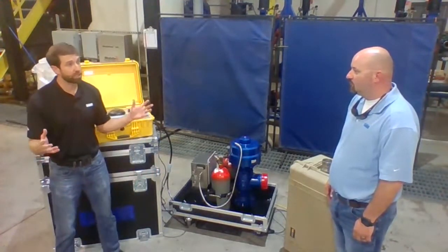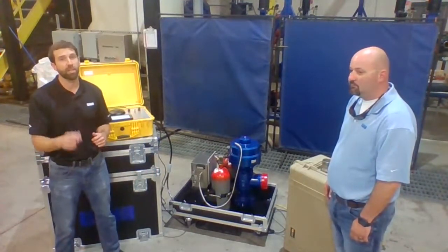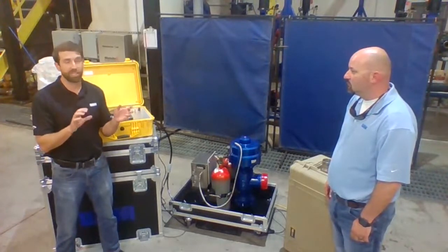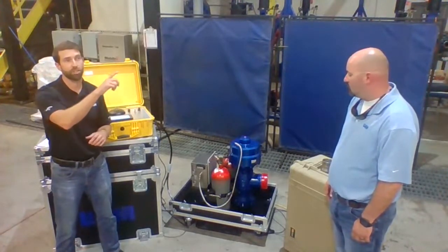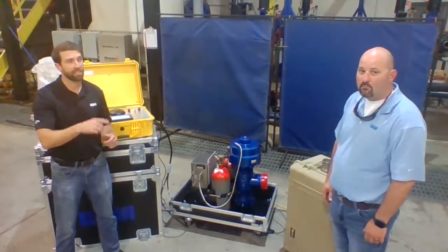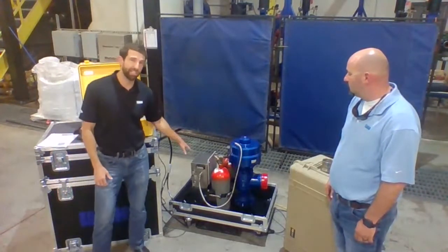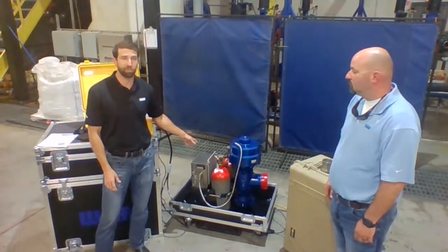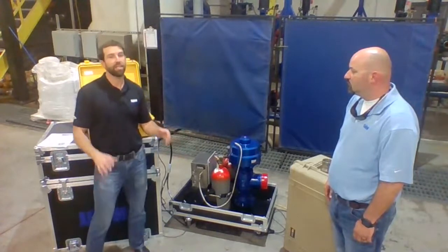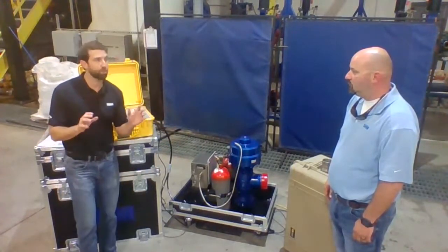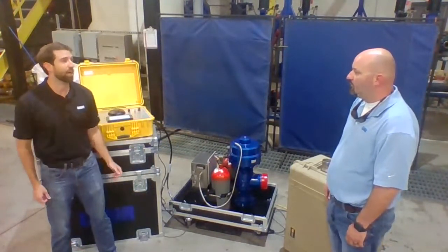That's all that's required to hook up. One thing to note here: you no longer need to use any manual regulators on your in-line supply into this valve box. It's got a built-in regulator to check the in-line pressure before it comes in, so we won't damage any components, and it lets you get away from those manual regulators that typically dump quite a bit of nitrogen.